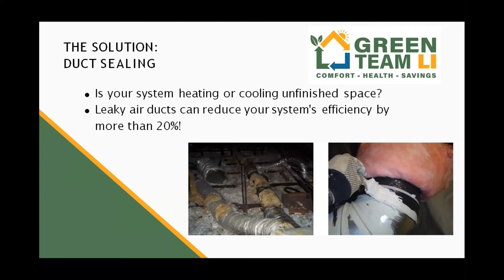And it's a good example in the picture on the lower left, where maybe an animal got in there, but literally sometimes we go and find things have fallen apart and become disconnected. And the picture on the right shows the solution: applying a latex sealant called duct mastic to the joints and sealing up those potential leakage points, and we can get the ductwork quite tight, pretty close to 100% getting to where it's supposed to go.